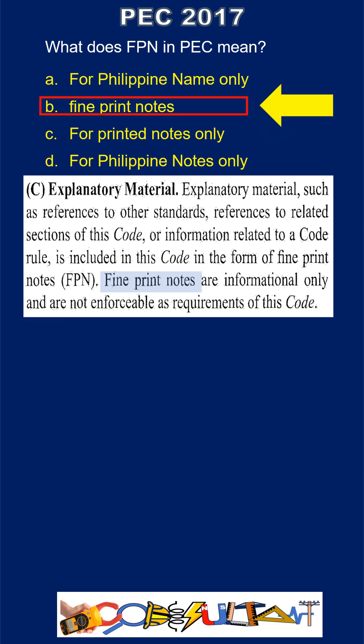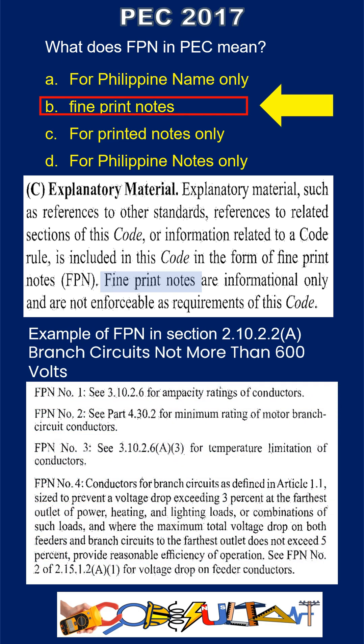Let's have an example of FPN. In section 2.10.2.2a, Branch Circuits, FPN number 4 states that the maximum combined voltage drop for both the feeder and branch circuit shouldn't exceed 5%, and the maximum on the feeder or branch circuit shouldn't exceed 3%. The code doesn't require us to do voltage drop calculations because they aren't involved in issues of safety, but that doesn't mean they aren't important.